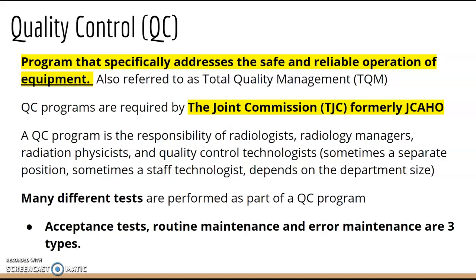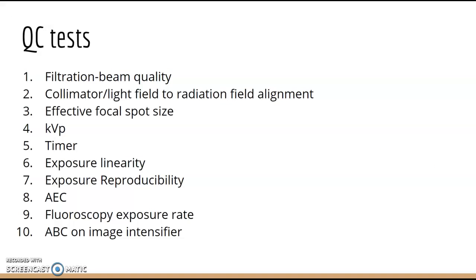QC involves you as technologists — you are the frontline people with the equipment and patients. There's also a lot of background testing performed by others, but you're really the frontline person to report when a machine isn't working properly. The three main types of QC tests are acceptance testing, routine maintenance, and error maintenance — focus on these for your board review.